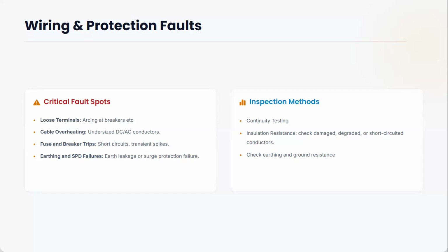So you now have the SPD in the system, the surge protector device. Because earthing has failed, those surge protector devices will just be there, because they work with the earthing. They have an earthing terminal, and the earthing has failed. They will just be there. So it's important to check all these protectors to make sure that they are in good condition.